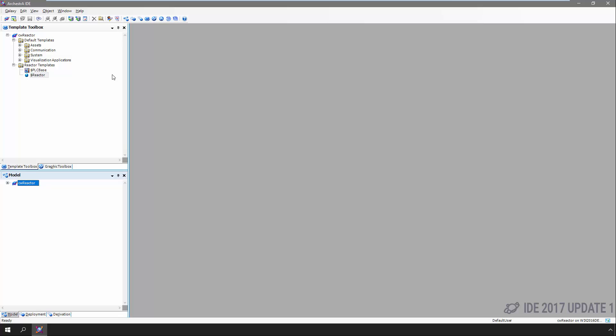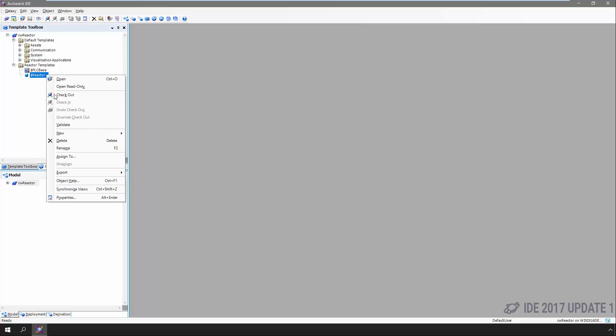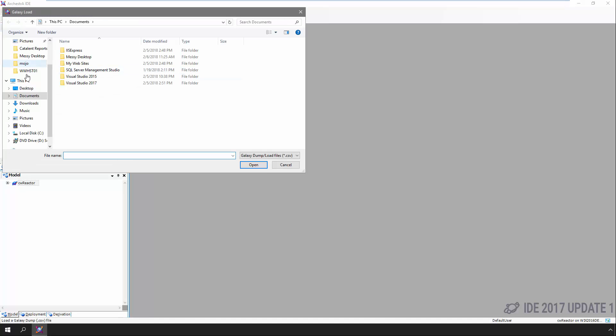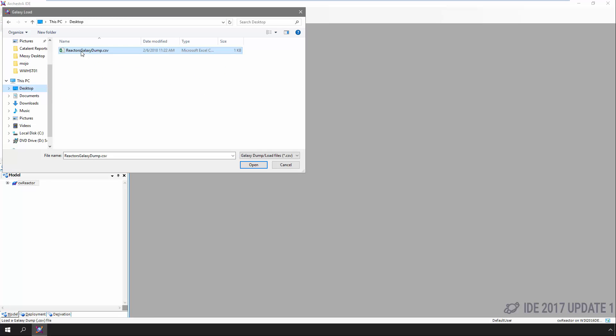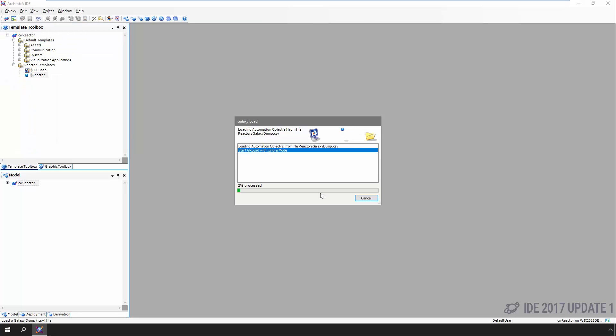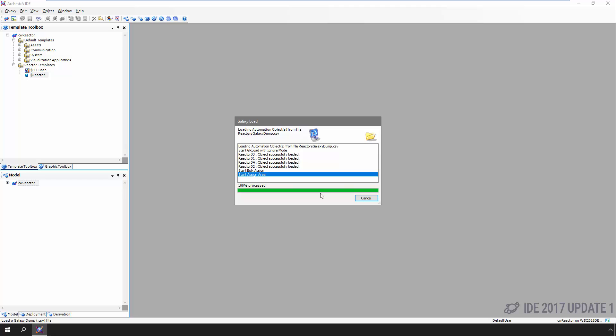Now we need instances of the reactor template to match what we have running in our plant. In this case, we'll say we have four reactors across two buildings. We could do this instantiation process manually — right-click, choose new, name it, drag and drop it — but to speed things up, we can just import a very simple CSV file that creates the instances for us. This is a method a lot of people overlook, but it's so simple you might want to give it a try.